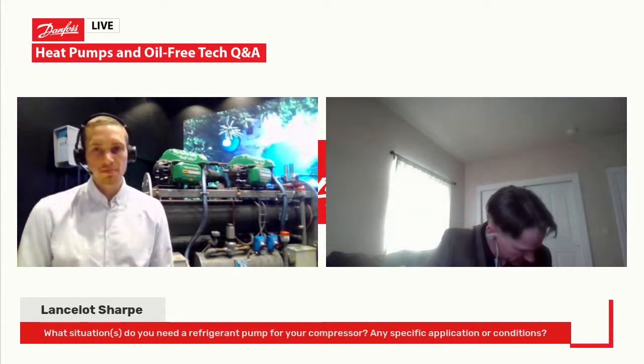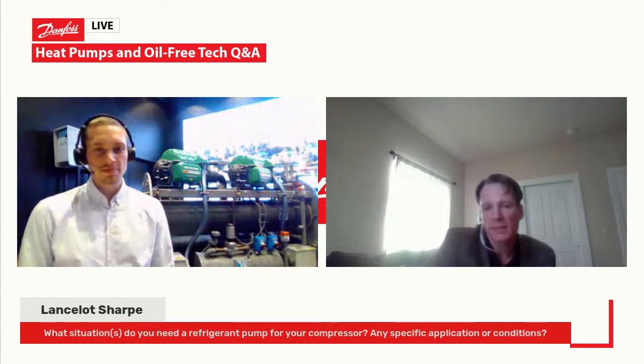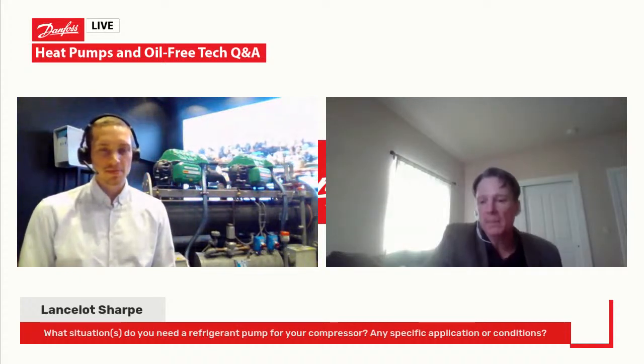Yeah, that ties back to the low lift discussion earlier for data centers. If you're going to operate below a certain pressure ratio, I can't remember the exact number, you need to enable the refrigerant pump, or incorporate a refrigerant pump, to make sure the power electronics gets the cooling it needs. So again, we can operate down to a pressure ratio of 1, but you need that liquid pump in there to make sure the power electronics gets the cooling.